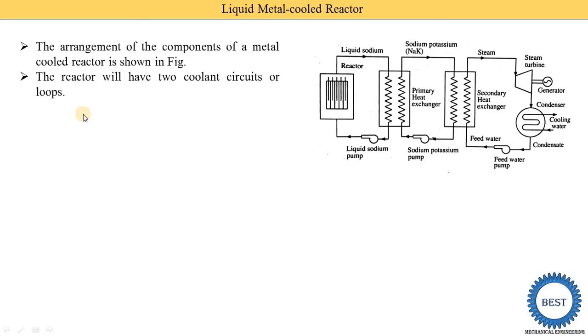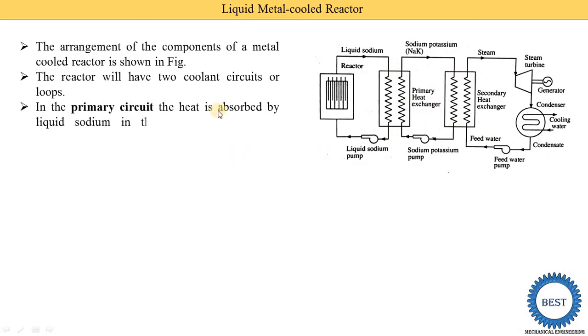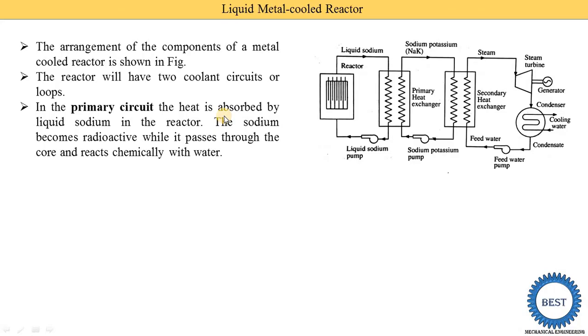The reactor has two coolant circuits or loops — a primary and a secondary. In the primary circuit, heat is absorbed by liquid sodium in the reactor. Fission chain reactions produce heat energy, which is absorbed by the liquid sodium. This sodium becomes radioactive as it passes through the core, and it also reacts chemically with water. The heated liquid sodium is then supplied to the primary heat exchanger.